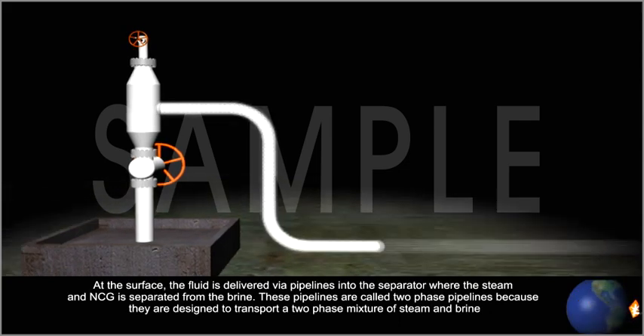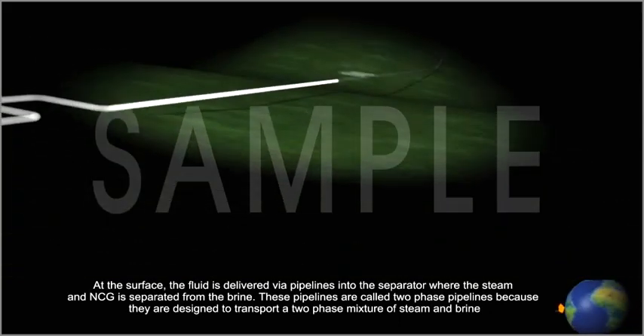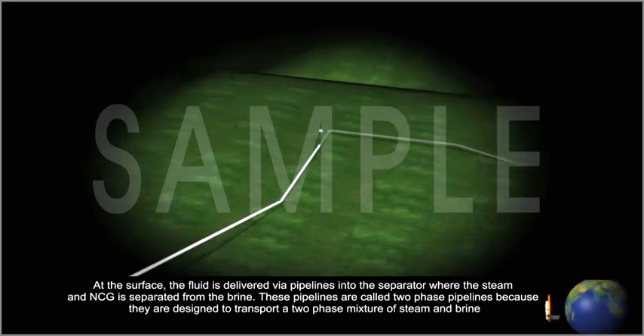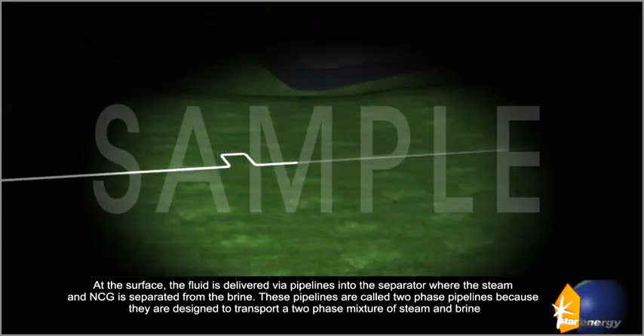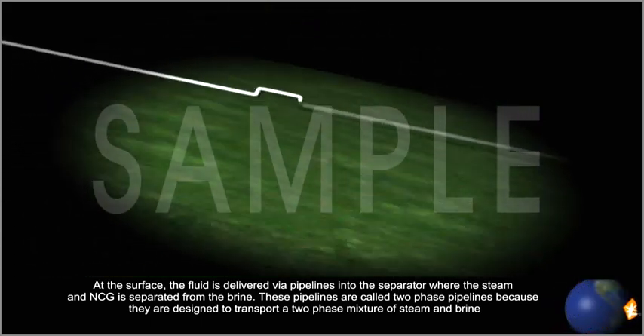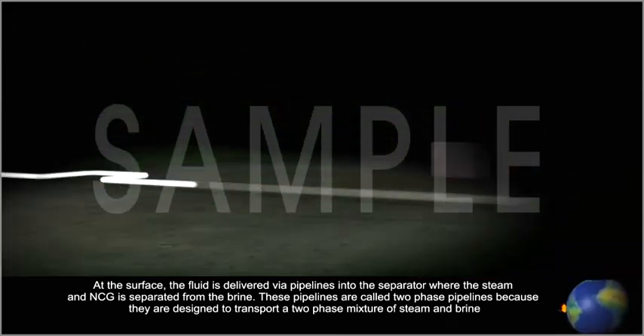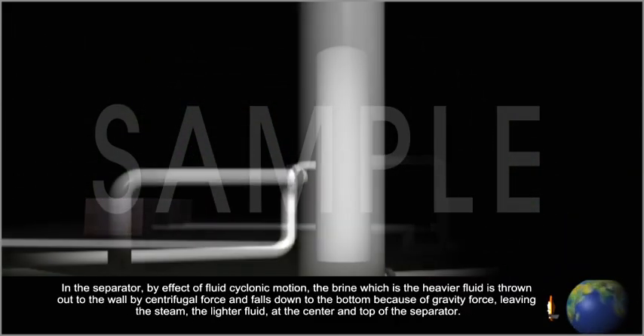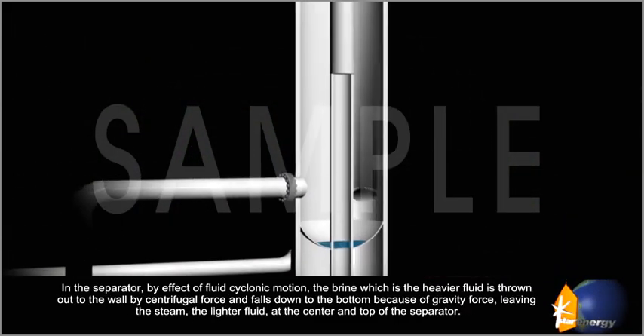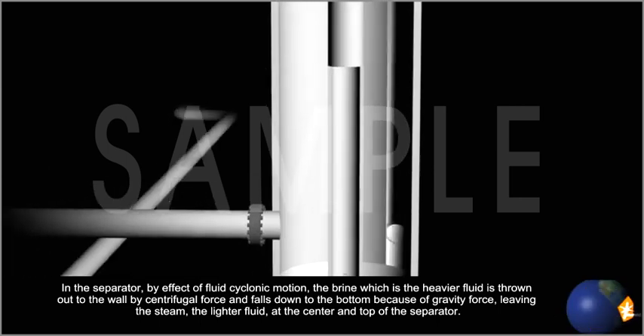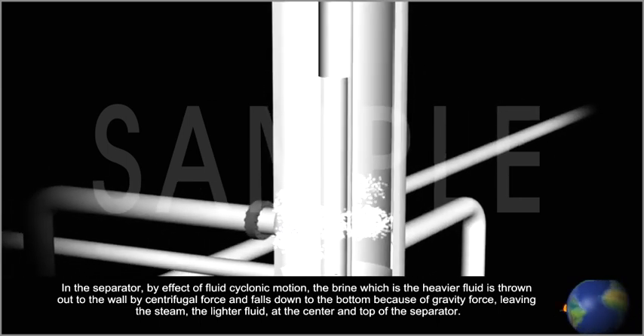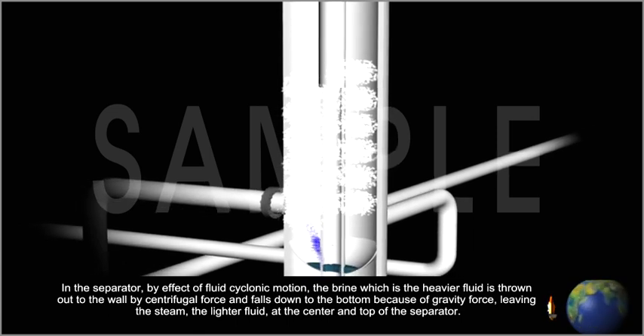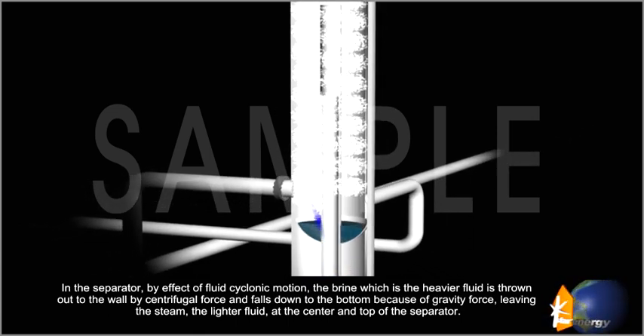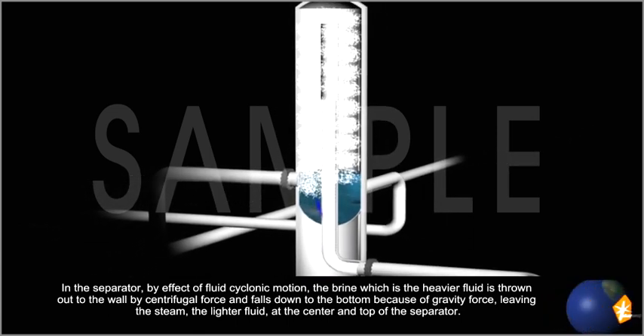At the surface, the fluid is delivered via pipelines into the separator, where the steam and NCG are separated from the brine. These pipelines are called two-phase pipelines because they are designed to transport a two-phase mixture of steam and brine. In the separator, by effect of fluid cyclonic motion, the brine, which is the heavier fluid, is thrown out to the wall by the centrifugal force and falls down to the bottom because of gravity force, leaving the steam, the lighter fluid, at the center and top of the separator.